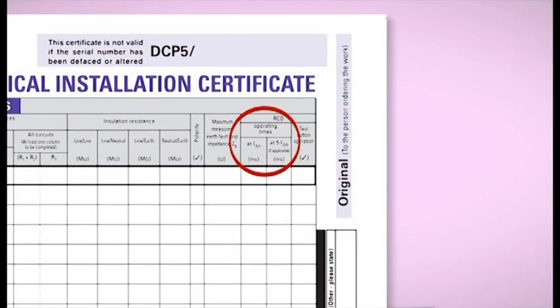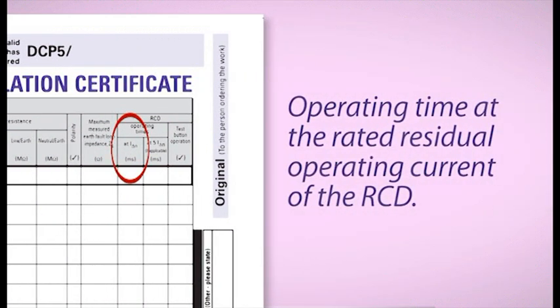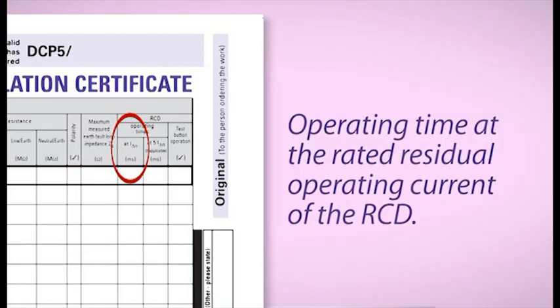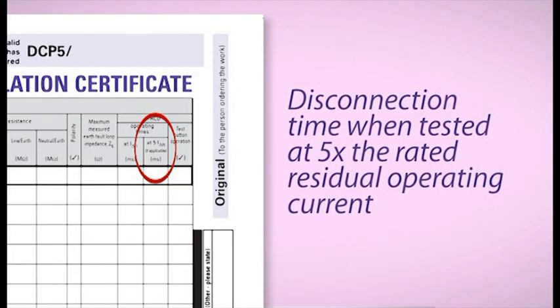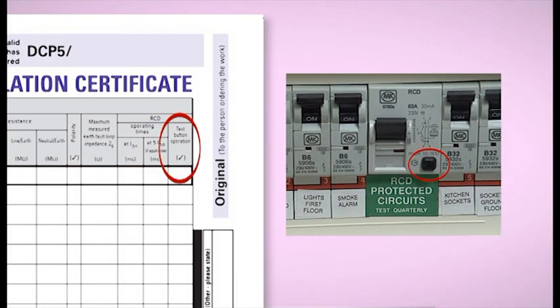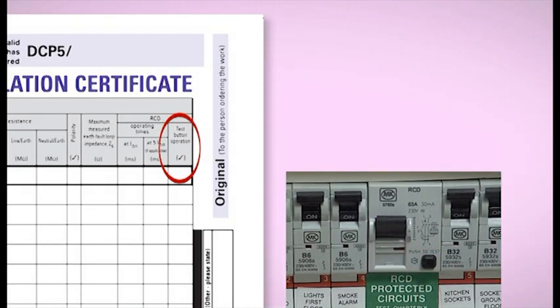Next, we have two columns for RCD operating times. The first is the operating time at the rated residual operating current of the RCD, which is required for all RCDs and RCBOs. The second column is for the disconnection time when tested at 5 times the rated residual operating current. This is only a requirement for RCDs installed to provide additional protection against electric shock. So RCDs with a rated operating current not exceeding 30 milliamps. There is a third column here for checking the operation of the RCD by pressing the manual test button. If the RCD operates, a tick shall be inserted here.